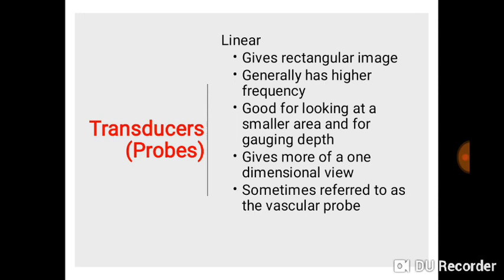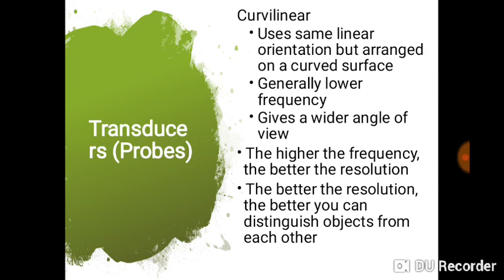Let's briefly look at a few types of transducers and probes. There is the linear probe, which we also recommend for breast ultrasound. The images it produces are rectangular. It generally has a higher frequency — ranging from 7.5 megahertz or higher — and is mostly used for superficial structures. It gives a one-dimensional view and is sometimes called the vascular probe, used to perform vascular studies since most blood vessels are relatively superficial.